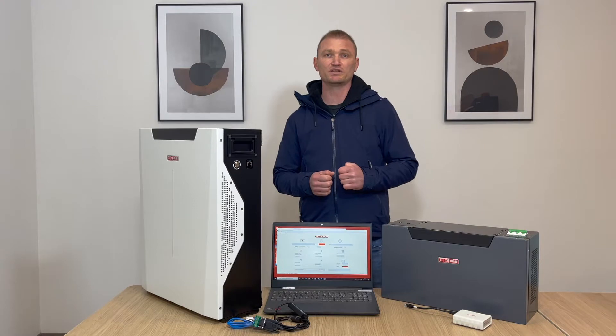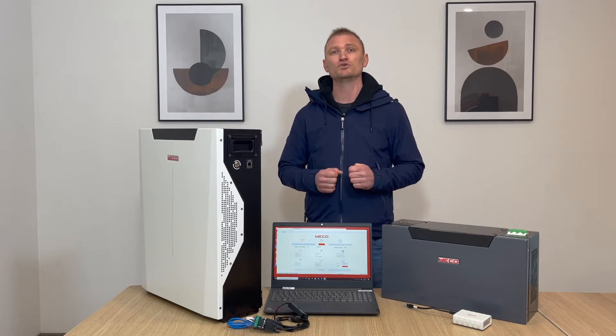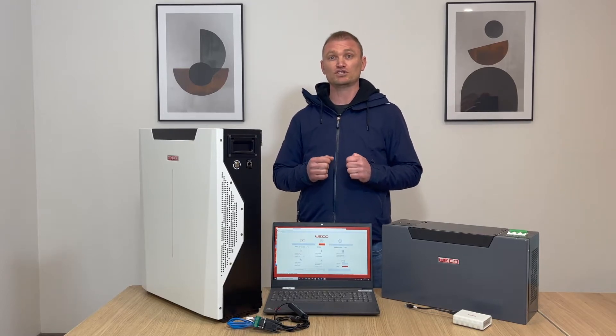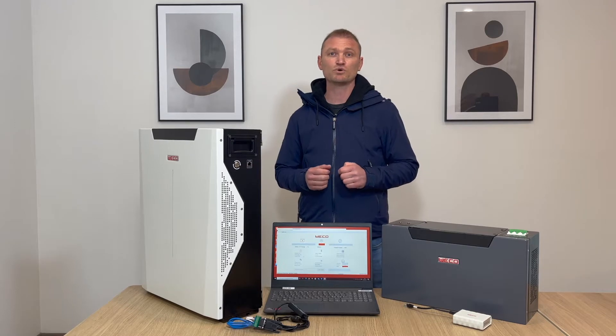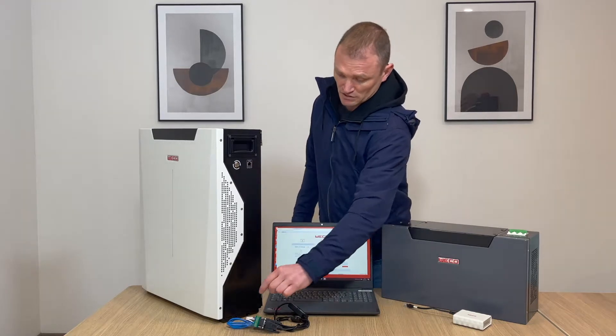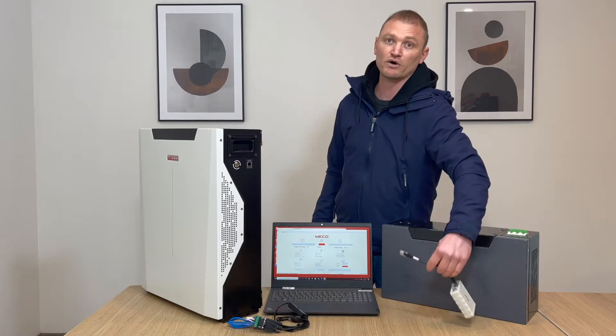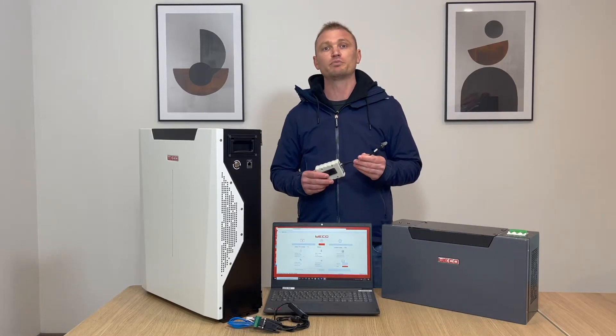All WECO batteries can be monitored through the WECO monitoring software that we suggest to use during the installation process. To use the WECO monitoring system it's necessary to add a computer with Windows 10 and a WECO USB RS232 serial converter. The connection with the WECO USB converter has to be made through the RJ45 network port on the side of the batteries next to the run button. The same port can be used to connect the USB device and the WECO app available on the App Store and Google Play Store.